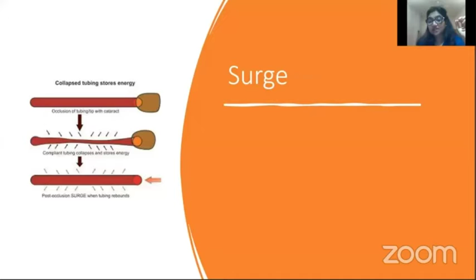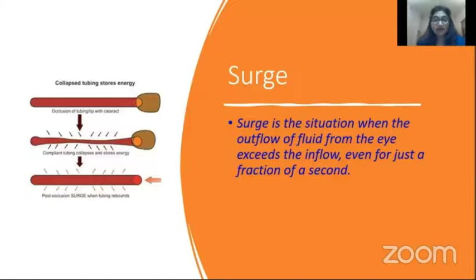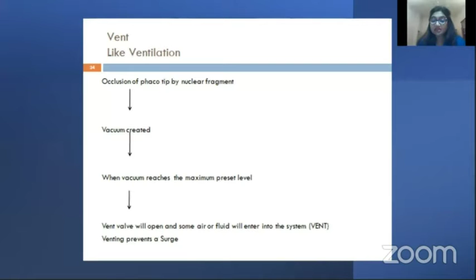This can be dangerous because once the anterior chamber is shallow, PC can come up and you can end up with a rent. This is prevented by something called venting. That is, when the vacuum reaches its maximum preset level, a vent valve will open and some air or fluid will enter into the system so that this collapse is prevented and the surge is prevented.